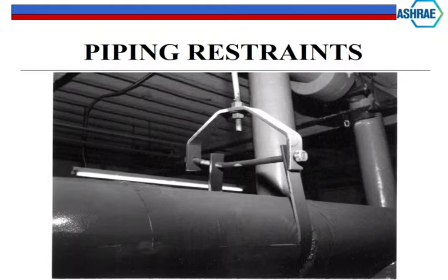There's a bunch of real easy fixes for that, and one of them is a piece of pipe. When the contractor is installing this, if he had put a piece of pipe on there that's bigger than the OD of that bolt, he could have saved that, because you never would have bent both the bolt and a piece of pipe. That is going to cost the contractor a couple of pennies. But now he's got to go back, support the pipe, take this apart, and put a new one in, hopefully this time with some pipe on there or some other form of bracing it.